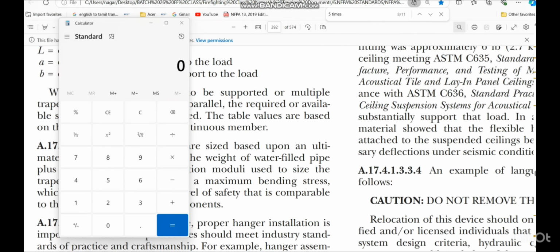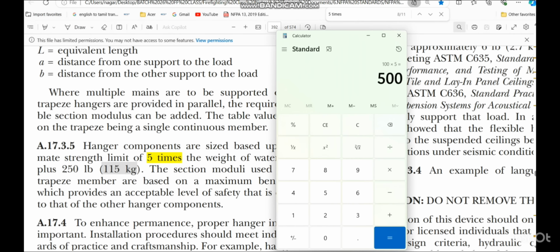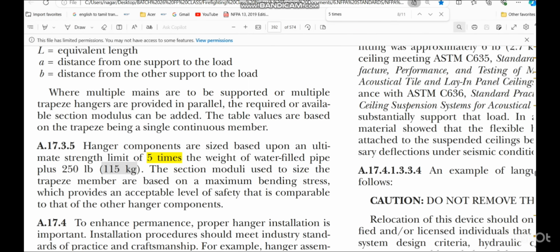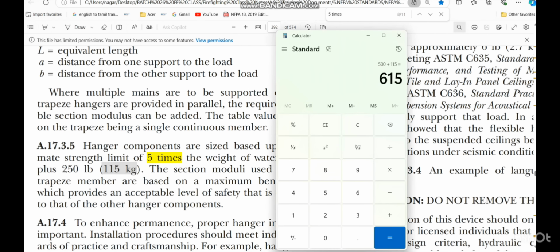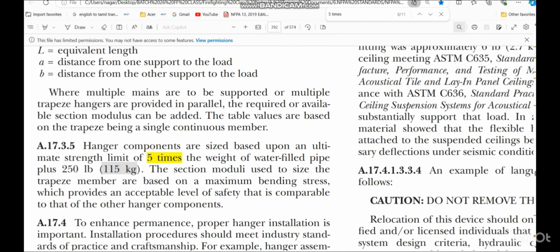Okay, for example, the water filled pipe weight is 100 kg. So we can say 5 times, so into 5, 500 kg. Additionally, plus 115 kg. So total, the hanger support should withstand this much load. That means 615 kg at each location. So this is the special requirement for the NFPA 13.